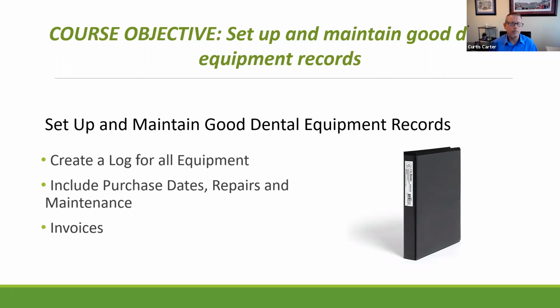This could also help you if you're having chronic issues with a piece of equipment. You can track it to that serial number, if you have multiples of the equipment. But if you ever get into a situation where you need a warranty replacement on equipment, occasionally there are pieces of equipment, I like to call them the Friday at 5 pieces of equipment, that have some chronic issues. If you've got a nice clean log of all the repairs that you've done to it, tied to the serial number and dated, you've got a pretty easy case to present to the manufacturer for a warranty replacement.